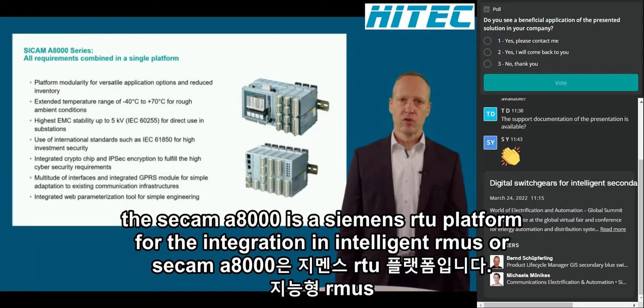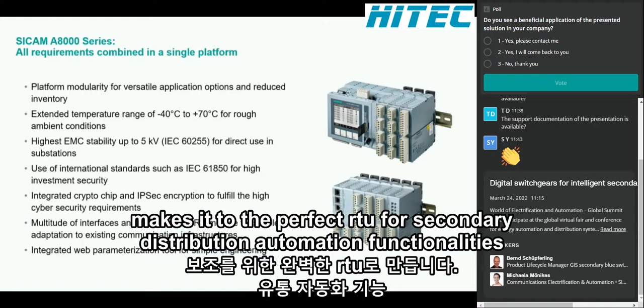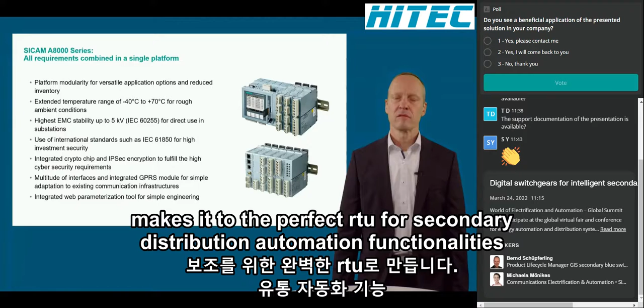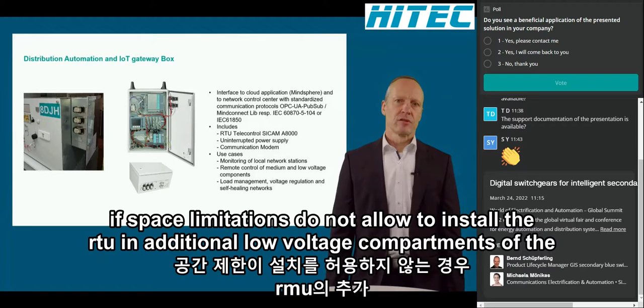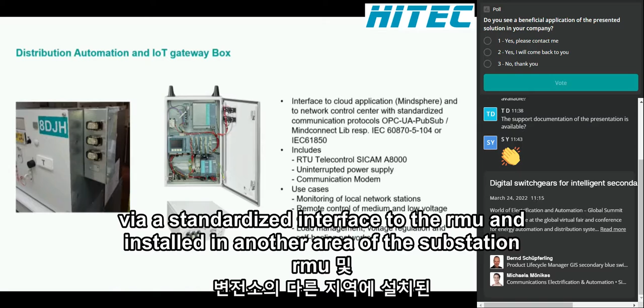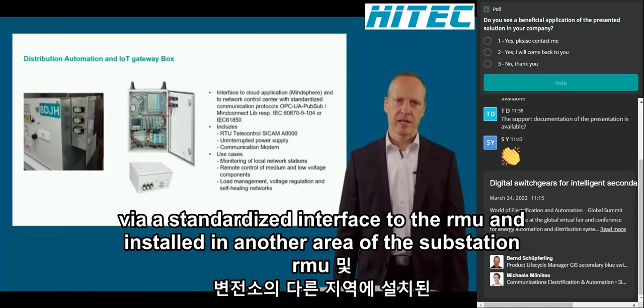The SICAM A8000 is a Siemens RTU platform for the integration in intelligent RMUs or substations. Various modules for analog and digital inputs and outputs, as well as a robust design for harsh environment conditions, together with integrated security and communication functions, make it the perfect RTU for secondary distribution automation functionalities. If space limitations do not allow installing the RTU in additional low voltage compartments of the RMU, we can also provide an external so-called distribution automation box, connected via a standardized interface to the RMU and installed in another area of the substation.